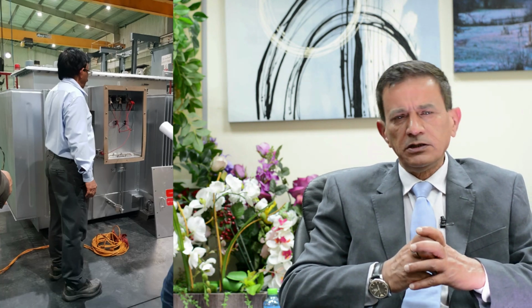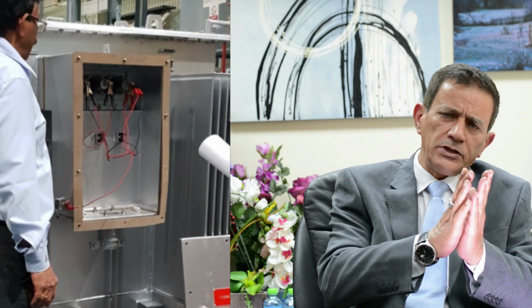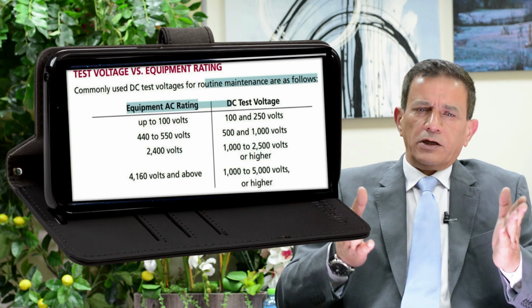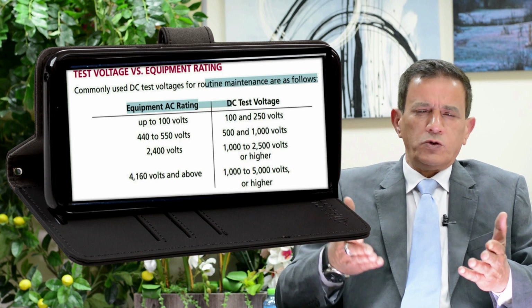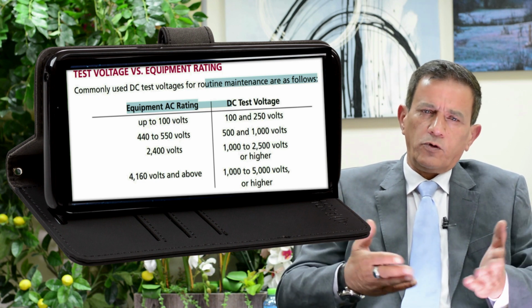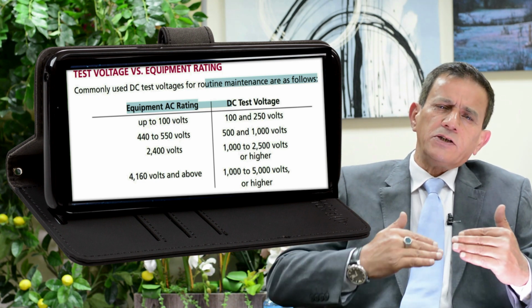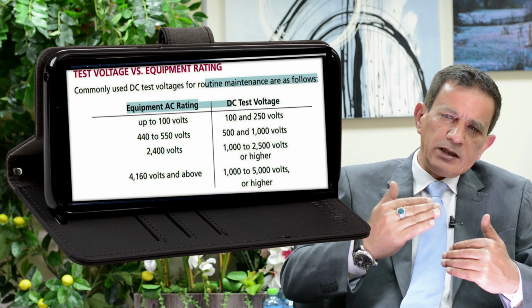To do this test for the transformer, the low voltage terminals will be shorted together, also the high voltage terminals, and there are three different measurements to be taken. Each measurement will be injected by a different voltage, because the voltage we apply to the insulation material is always dependent on the system voltage. We can use 500 volt, 1 kilovolt, 2.5 kilovolt, 5 kilovolt, even more, based on the insulation level of the electrical system.